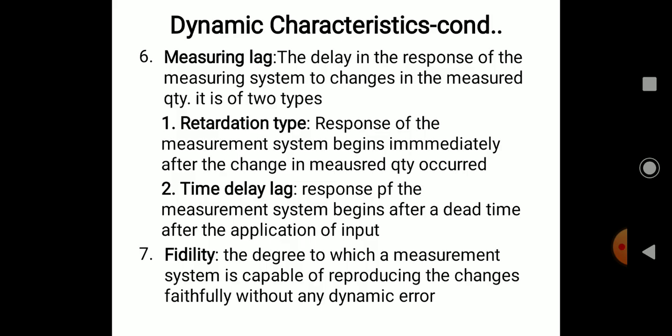Measurement force and contact force are factors here. Suppose we are giving more force on a micrometer; we use a ratchet stop to avoid the fidelity error, because irrespective of the operator or the component, the ratchet stop gives a constant measuring force over a number of readings. So the dynamic error due to fidelity can be avoided.